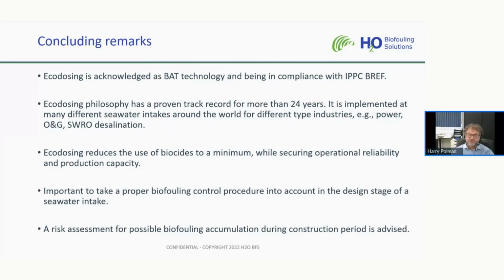Ecodosing reduces the use of biocides to a minimum while securing operational reliability and production capacity. It proved that by reducing the amount of biocide, you actually improve operational reliability and biofouling control and can guarantee production capacity. It's important to take a proper biofouling control procedure into account in the design stage of a new plant, in the design stage of a new seawater intake. In addition, as mentioned earlier, there is a risk during the construction of a seawater intake. So a risk assessment of a possible risk for biofouling accumulation during the construction period is strongly advised to prevent head loss during the commissioning of the plant itself.